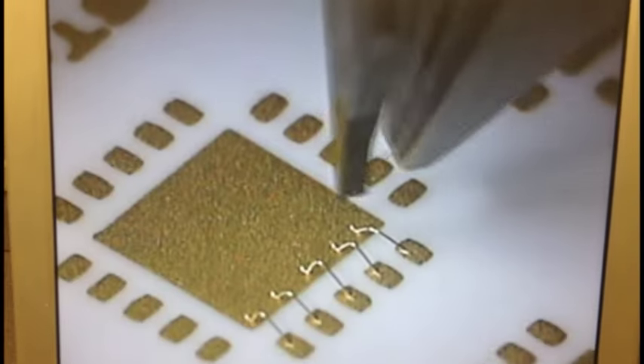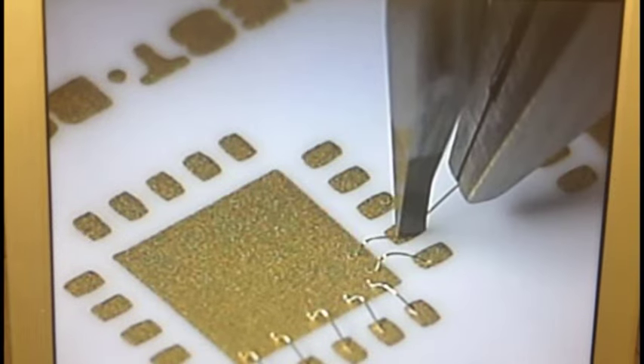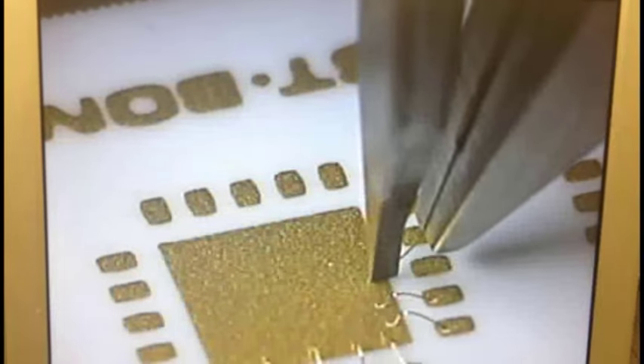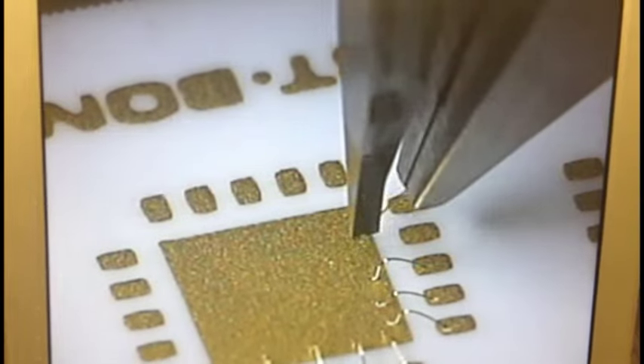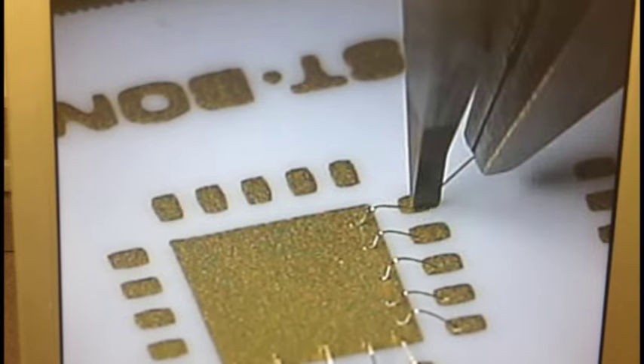The 7476 performs ultrasonic, thermosonic, and thermocompression bonding. Range of movement of the tool by the manipulator control is 562 thousandths vertically and 625 thousandths in a horizontal direction.